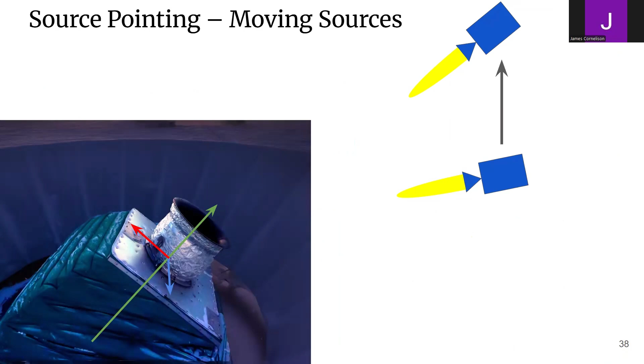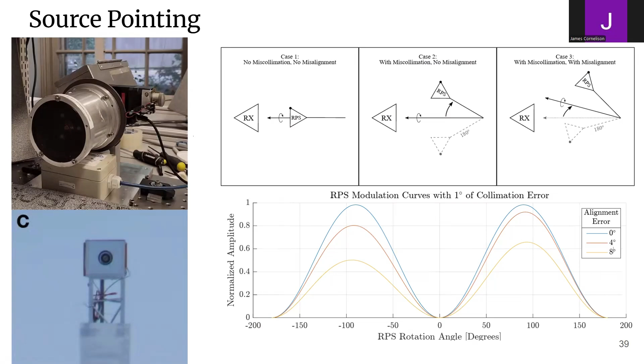Likewise, if your source rotates, like ours does on Bicep, you must ensure that the source is properly collimated. That is, that its pointing direction is aligned with the axis of rotation. If not, the pointing direction changes as the source rotates, adding an unwanted angle-dependent amplitude variation to the modulation curve.